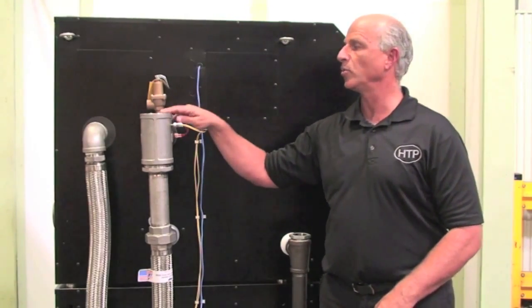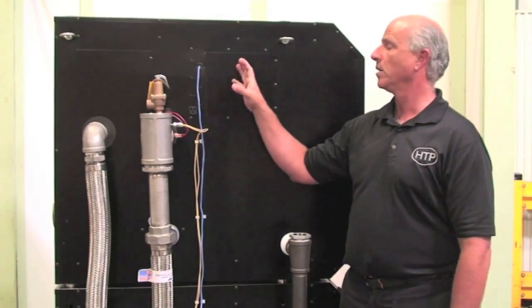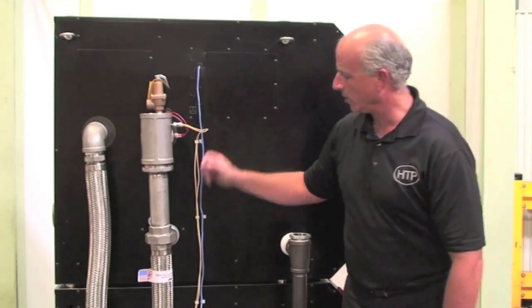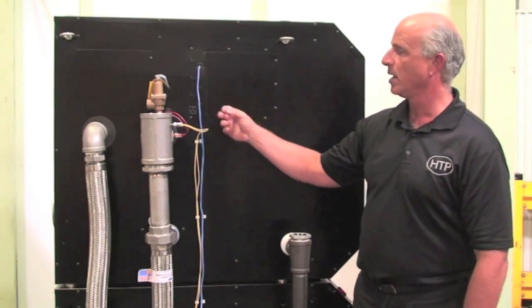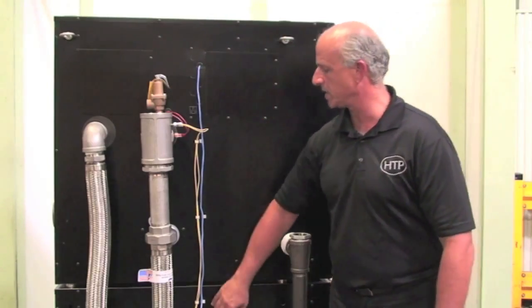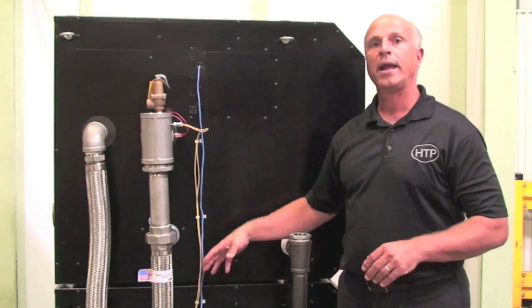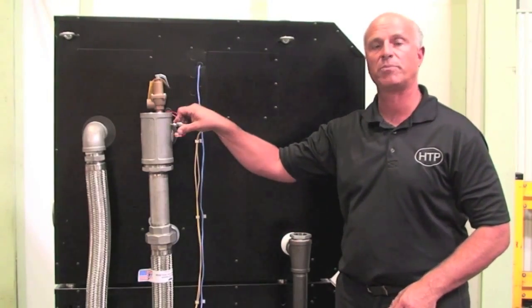This sensor will tell the master boiler, the main boiler, what to do. We have this communication cable, and the master will send a signal down to the follower if needed to come on and modulate to maintain a set point on this supply sensor.